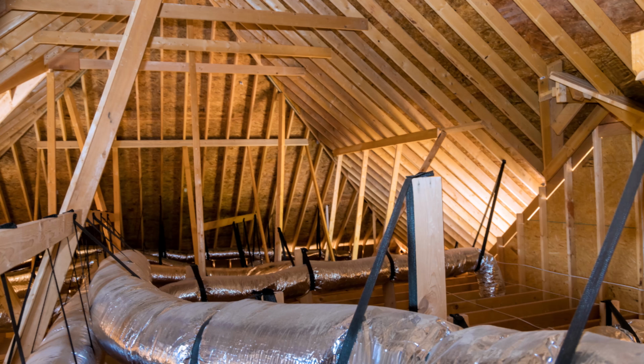I also want to mention something else I find in these spaces regularly: ductwork. A lot of knee wall attic spaces have supply and return ducts running through them. When I'm up there, I'm looking for leaky duct connections, disconnected flex duct, crushed flex duct, and ducts with little or no insulation on them. If you've got a duct leak in a 140-degree attic space, you're dumping conditioned air directly into the attic. So while you're up there fixing the knee wall, make sure to check out the ductwork too.